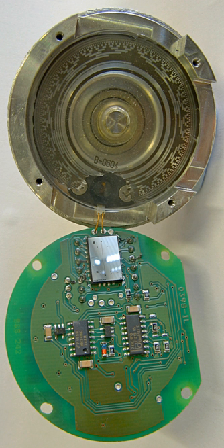Topic: Incremental encoder. The rotary incremental encoder is the most widely used of all rotary encoders due to its low cost and ability to provide real-time position information. The measurement resolution of an incremental encoder is not limited in any way by its two internal, incremental movement sensors. One can find in the market incremental encoders with up to 10,000 counts per revolution, or more. Rotary incremental encoders report position changes without being prompted to do so, and they convey this information at data rates which are orders of magnitude faster than those of most types of absolute shaft encoders.